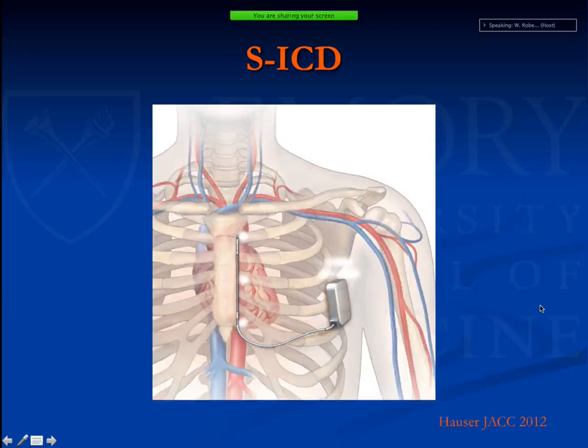And the person behind its design is Gust Bardy, who's an electrophysiologist. This is really a simple system. It's a large generator that's placed between the anterior and the posterior axillary line at the level of the 4th and 5th rib. Then there's a lead tunneled under the skin to be placed parallel to the sternum. This lead has a coil, which is used for defibrillation, and 2 electrodes for sensing, one here and one here. The sole purpose of this defibrillator is really just to shock patients from VF. It doesn't have all the bells and whistles of a transvenous ICD.